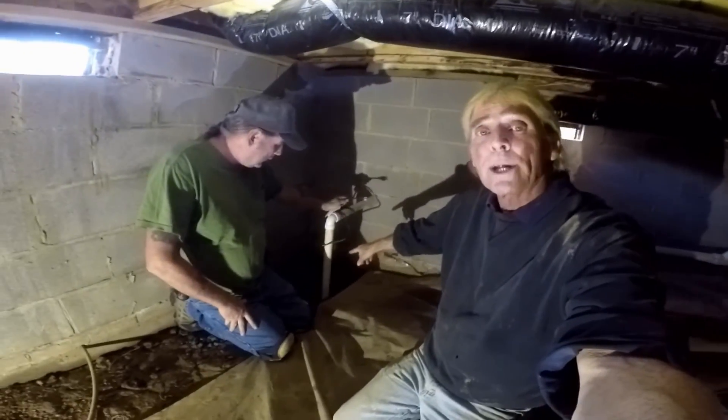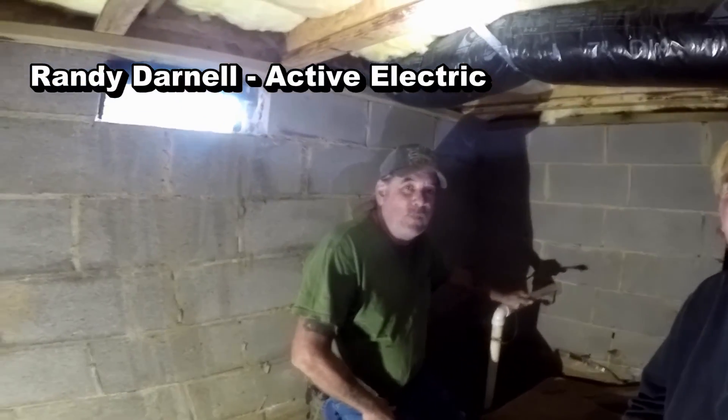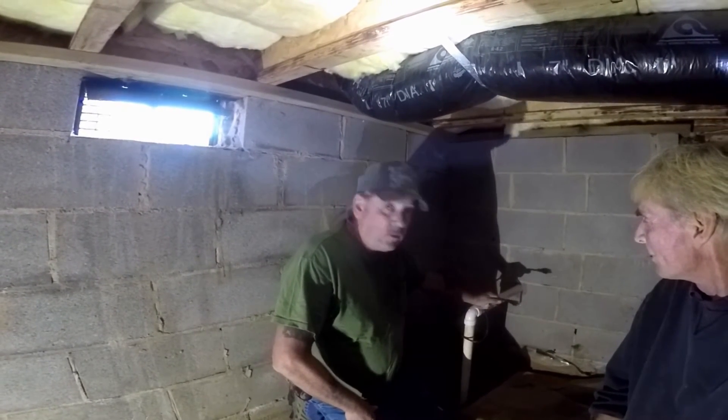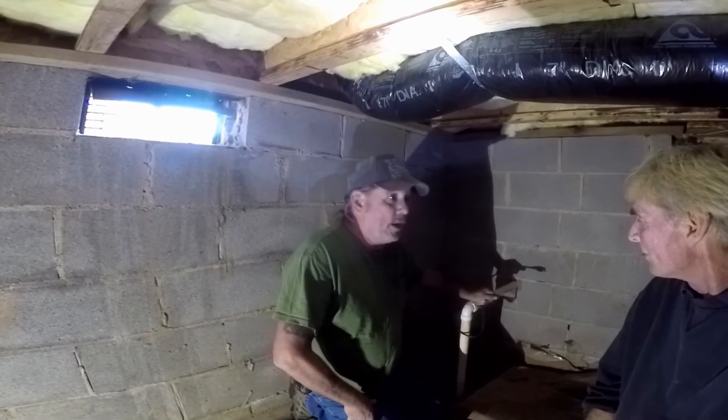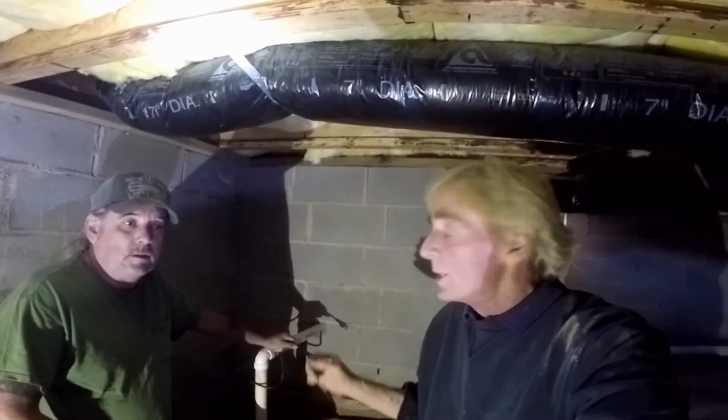We just finished putting in the Zoeller M53 sump pump out here. We had a water problem in the crawl space. As we finished, the electrician we use and recommend highly — Randy Darnell with Active Electric, here in Charlotte, North Carolina — just pulled up on the job site. He's going to install an outlet for this sump pump. It's required to be on a 20-amp circuit with GFCI protection. So if you're doing the sump pump yourself, make sure you get an electrician out to do this electrical work. It needs to go into a GFCI on a 20-amp breaker.